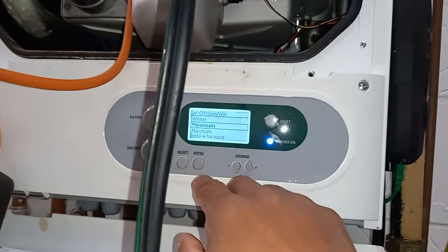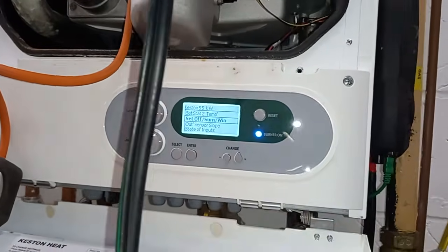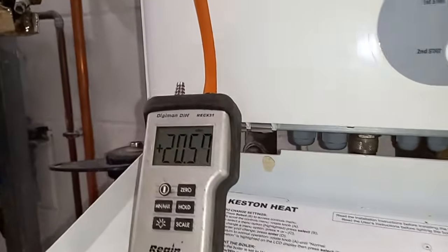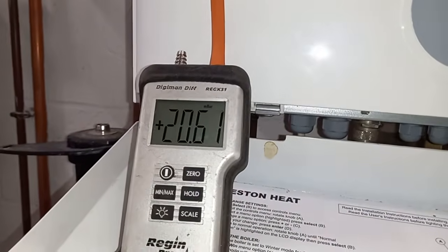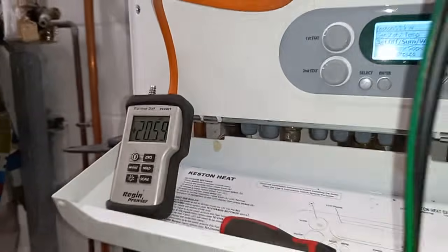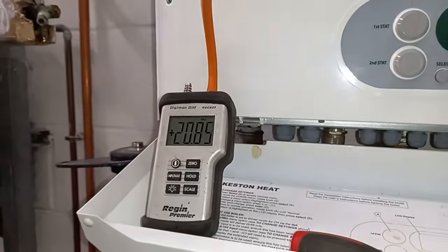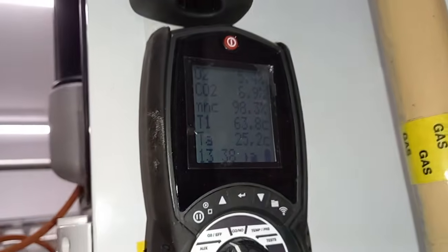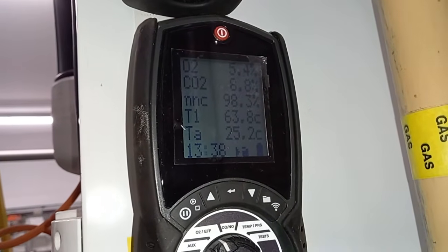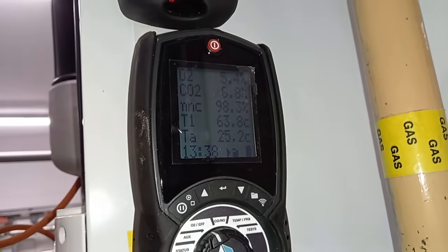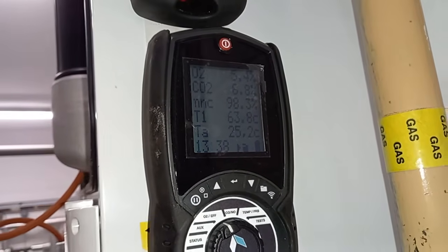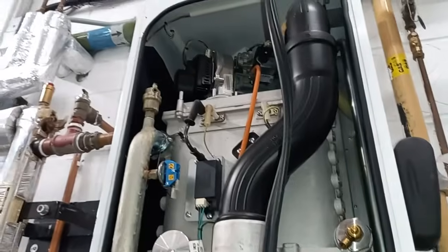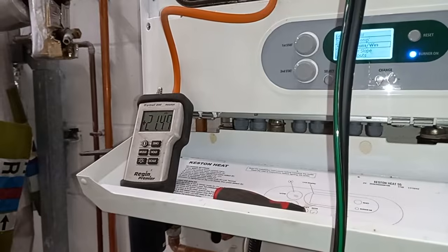If I hit select here now, I could go to minimum and press enter. And then I should see a difference in my working pressure. My working pressure should be different when I'm in low fire. And even my combustion, eventually my flue temperature, even though it's at 63 here, it should drop. My flue temperature should drop a little. So it's at 63 there, but it should go down. My fan is ramping down in speed as well.